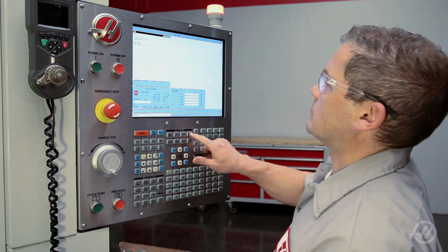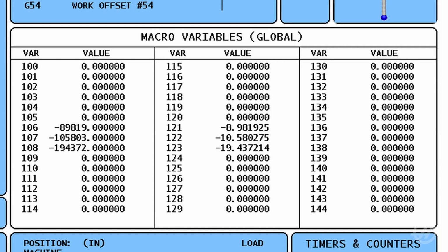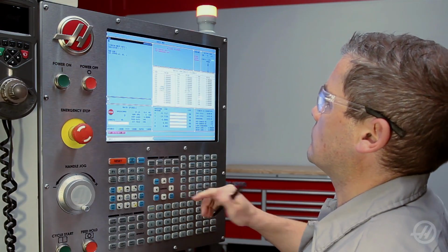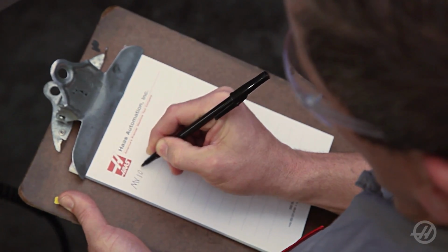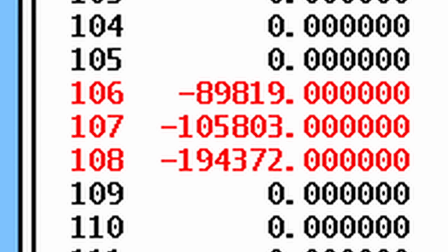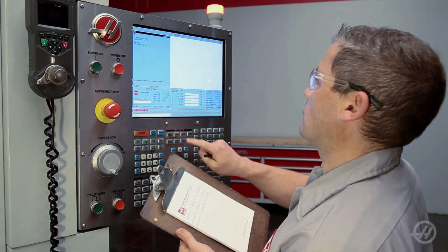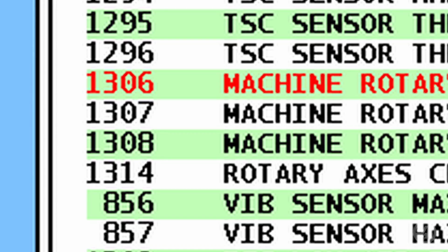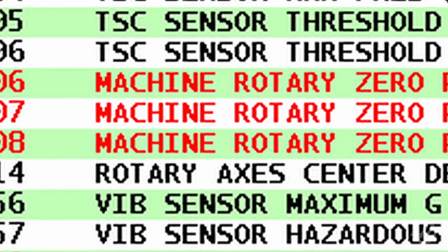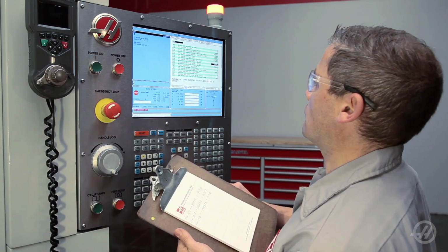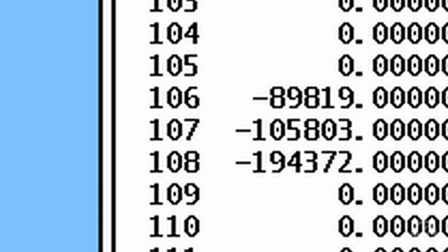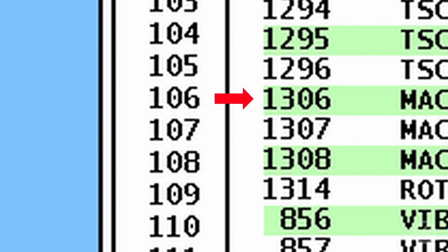Press Current Commands and press Page Up repeatedly until you reach the macro variables screen. Press the right arrow several times to get to variable 106. Carefully record the values displayed for macro variables 106 through 108. Change the existing parameter 1306, 1307, and 1308 numbers to these new values. Macro variable 106 corresponds to parameter 1306. Variable 107 corresponds to parameter 1307, and variable 108 corresponds to parameter 1308.